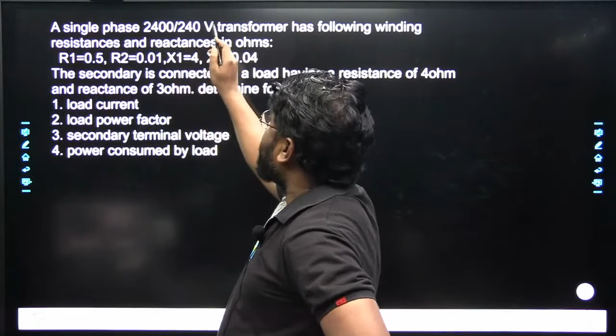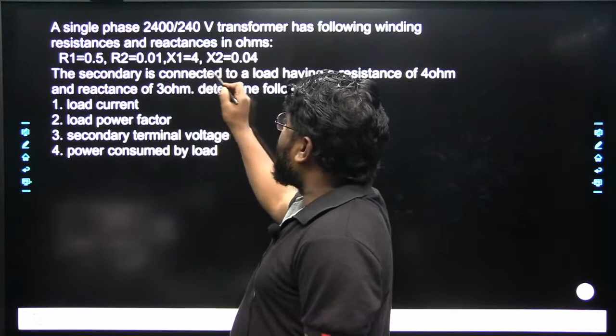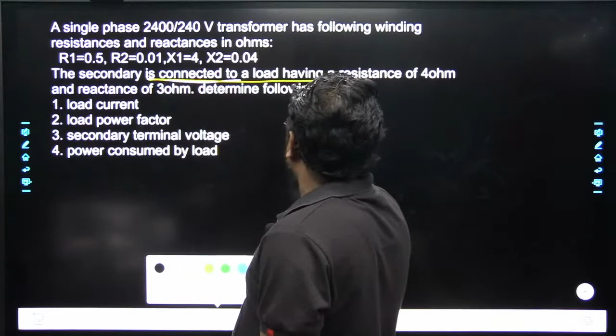Next, how do we get the percentage reactance of the transformer referred to the secondary side of the transformer? Similarly, this is also equal to the per unit reactance referred to the secondary side into 100. So 0.13 into 100 is equal to 13%. Got it? Yes, very good. That is equal to 13%.